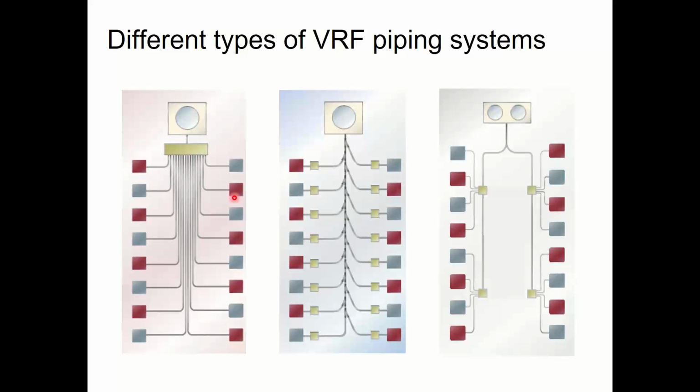Right? So you might want to do it that way. Depends on how your building is laid out. These pipes now become fairly long, and there's a lot of them. So if my building is laid out as a long, skinny building, this pipe drawing on the left would have a lot of piping compared to the middle drawing. But the drawing on the left would have fewer piping connections, so fewer places to have a field error. But I have to buy more pipe. Versus if my building was more squarish, then maybe it becomes more equal.